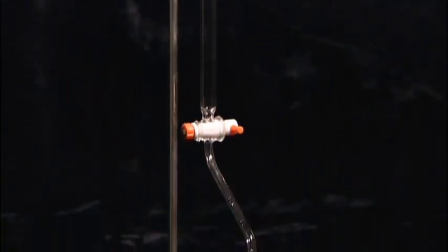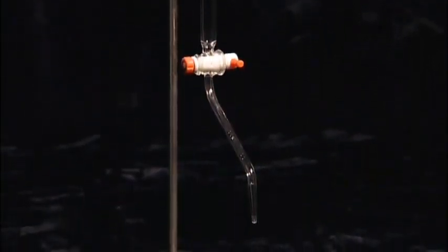We are now ready to perform the calibration of the gauge. As stated earlier, the calibration consists of introducing a known amount of water into the gauge over a known period of time and recording the output from the gauge. We have chosen a 50 milliliter burette. We will attach the burette in a fashion so that it will allow a known amount of water to be introduced into the gauge. At this time, let's record the make, model, serial number of the rain gauge sensor.